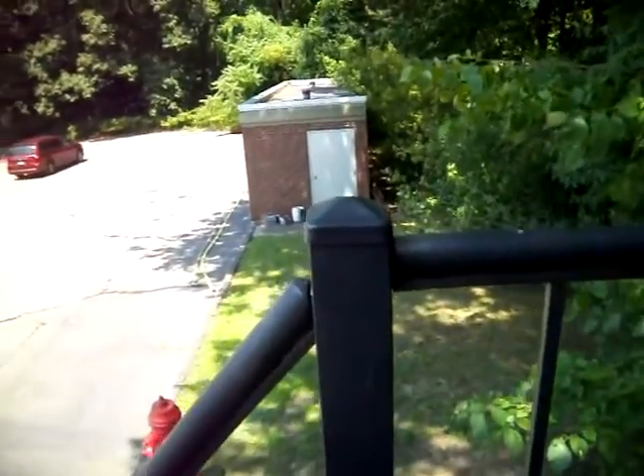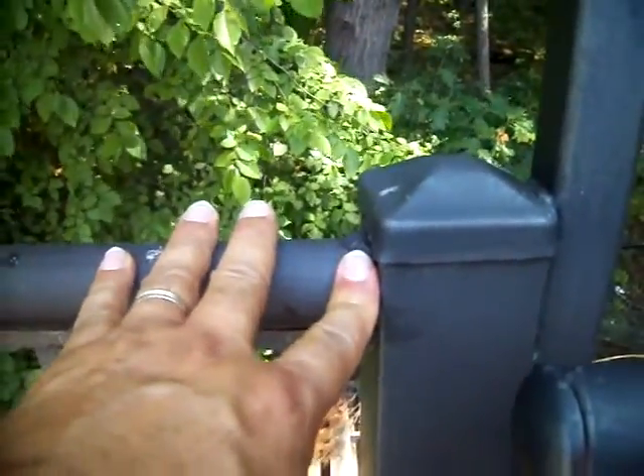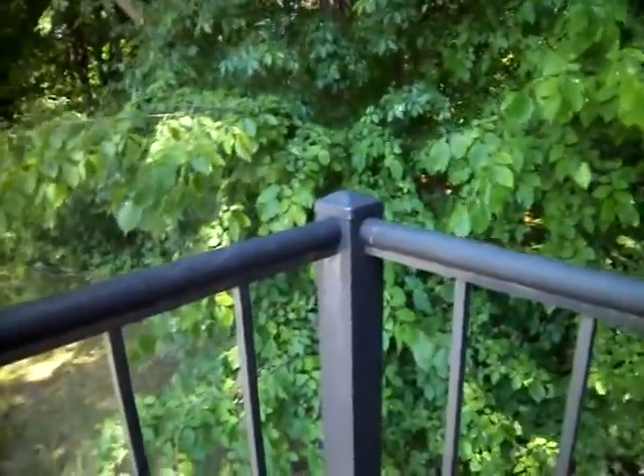The disclaimer says, to the best of my information, knowledge, and belief, the fire escape is in conformity with the Mass Building Code today. So if you want guarantees, guarantees come in the form of certification or in the form of a load test. So we can spot repair this fire escape and load test it completely and lateral load test it. That'll get you a guarantee. Or we can refurbish the entire fire escape and we avoid the load test because we certified. Mass Building Code 1001.3 says examine, test, or certify. Certification means refurbish 100%, and that will get you a confidence test with no disclaimers.